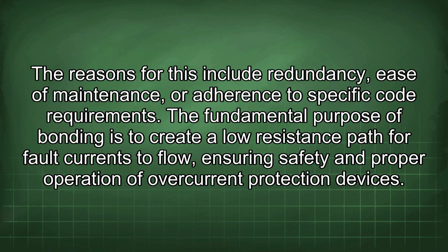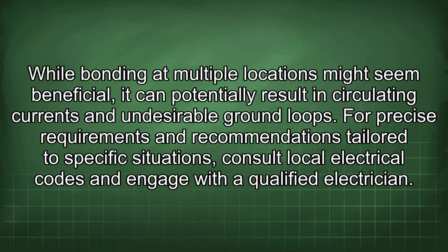The fundamental purpose of bonding is to create a low-resistance path for fault currents to flow, ensuring safety and proper operation of overcurrent protection devices. While bonding at multiple locations might seem beneficial, it can potentially result in circulating currents and undesirable ground loops. For precise requirements and recommendations tailored to specific situations, consult local electrical codes and engage with a qualified electrician.